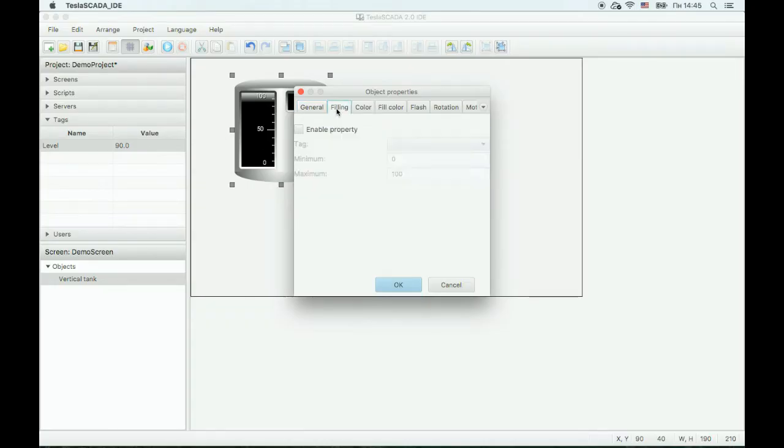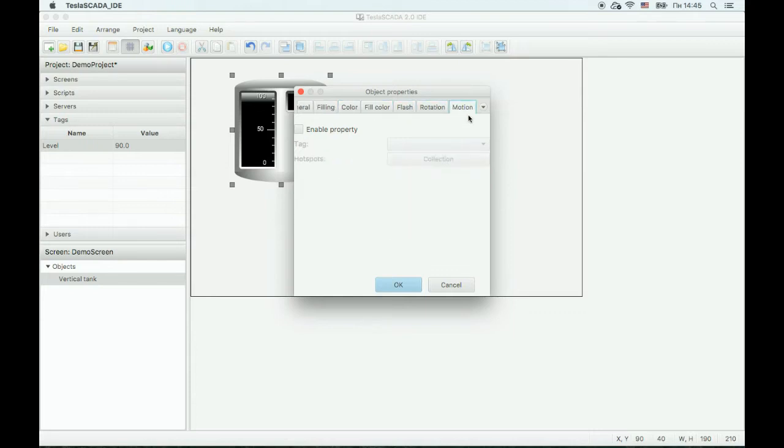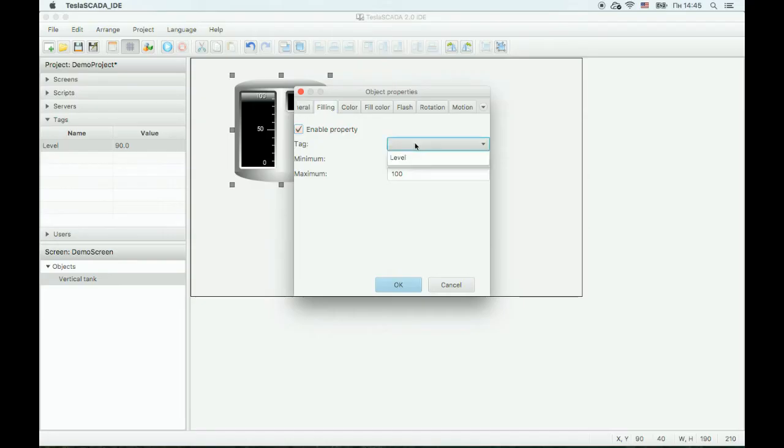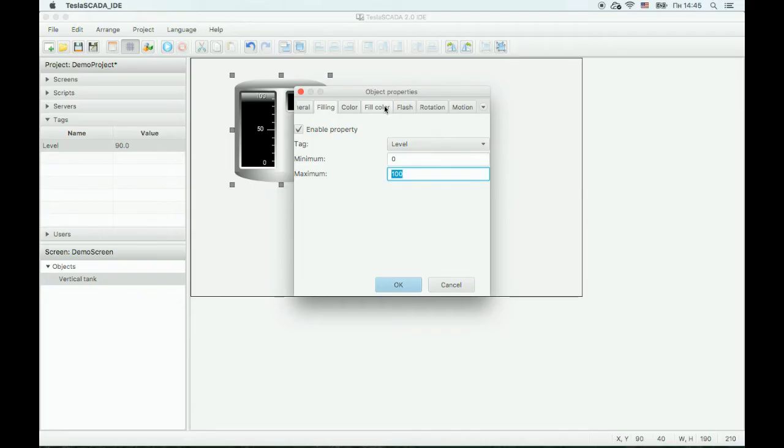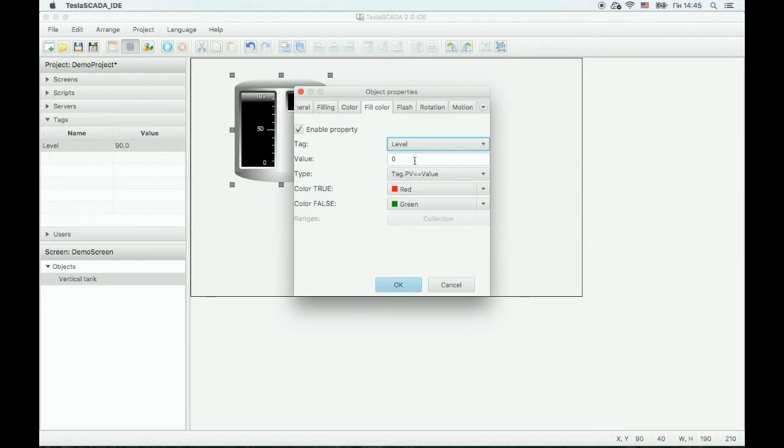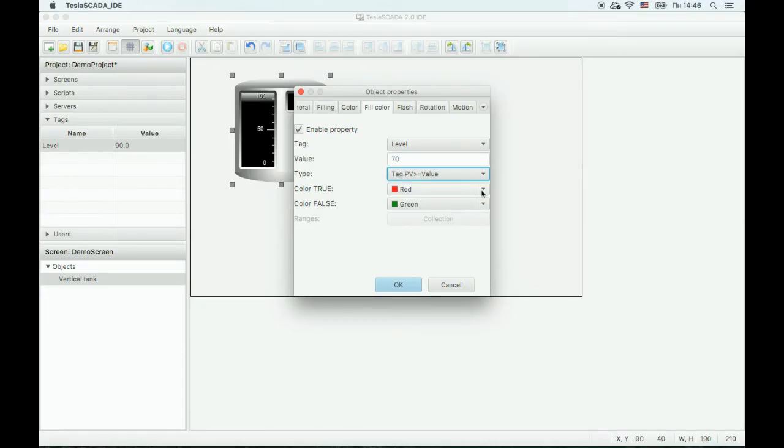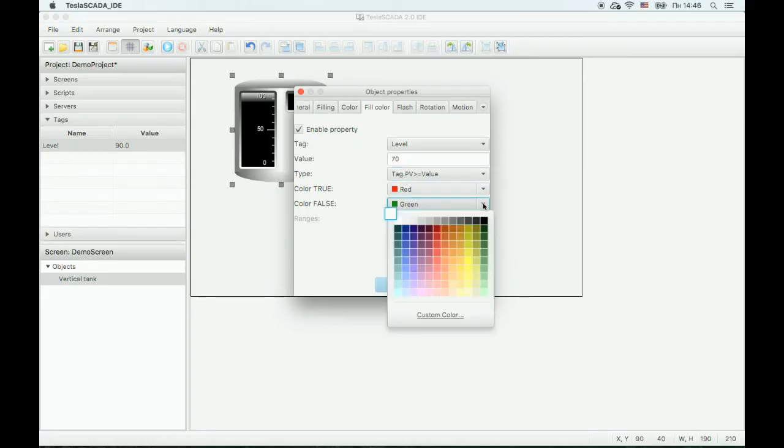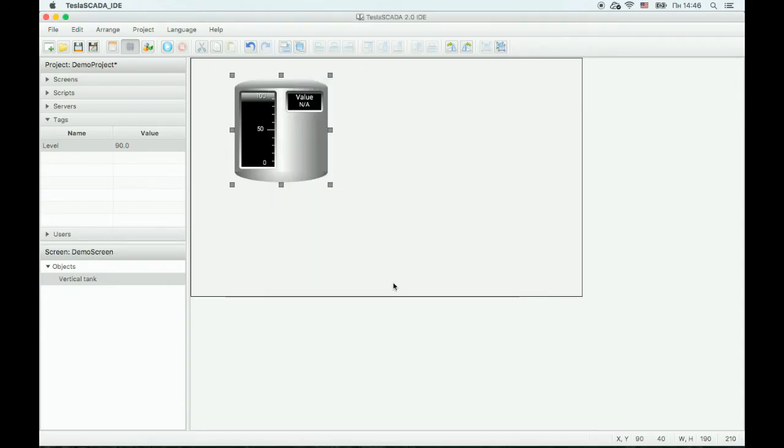In other tabs, you can change dynamic properties of this object. Let's change the filling property. Bind this property to the level tag and adjust minimum and maximum fields if you want. Also bind the fill color to the level tag. If the value is higher than 70, the filling will change to red. If below, the color will be green. OK.